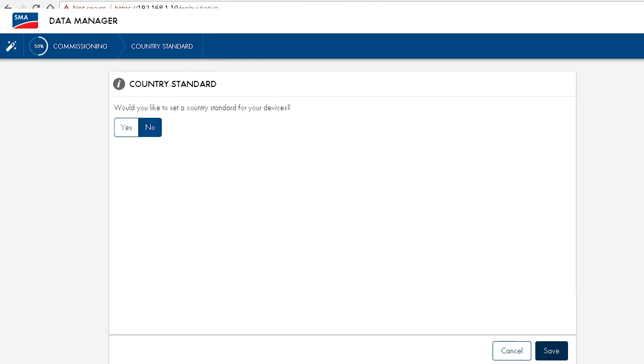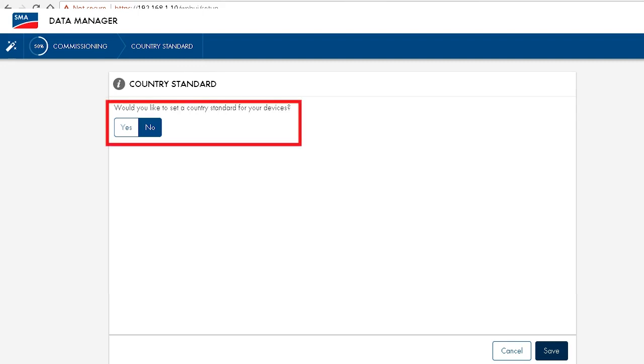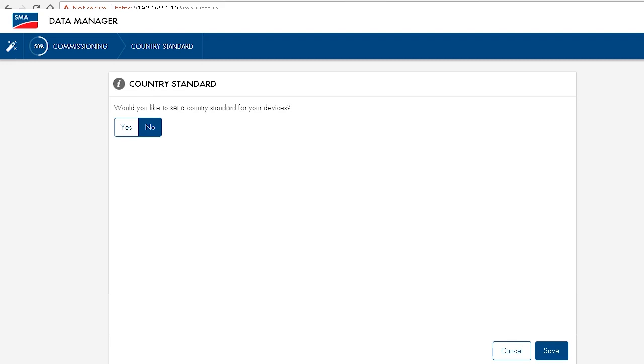The following step is very important in my opinion, as it means a big simplification in setting up the complete site. By selecting yes at this option here, the chosen country standards will automatically be transferred to all connected SMA devices. So you just have to choose it once and the rest of the setup work will be done by the data manager. Also, the entry of a grid guard code is not necessary anymore.